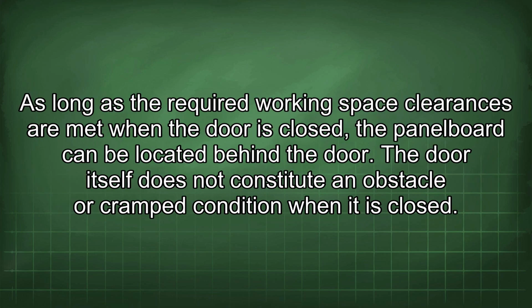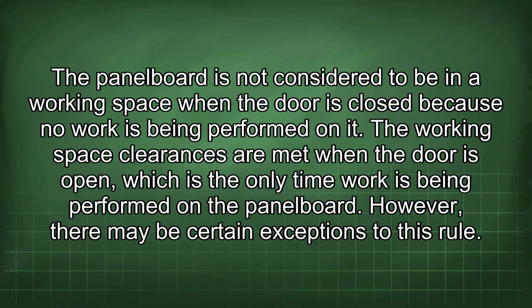As long as the required working space clearances are met when the door is closed, the panel board can be located behind the door. The door itself does not constitute an obstacle or cramped condition when it is closed. The panel board is not considered to be in a working space when the door is closed because no work is being performed on it. The working space clearances are met when the door is open, which is the only time work is being performed on the panel board. However, there may be certain exceptions to this rule.